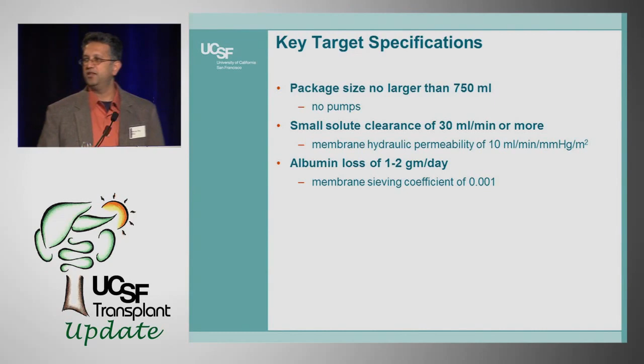Third, we need a membrane that doesn't lose albumin, but you have to say, what's an acceptable loss if we had to lose some albumin? What's the sieving coefficient? We set that to be 1 to 2 grams. And then fourth, we are operating in ultrafiltration mode. If you take 30 milliliters of clearance and multiply that by 1440 minutes in a day, that's about 45 liters.